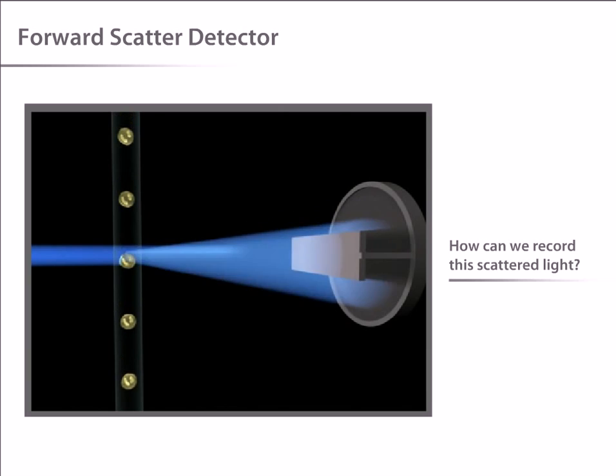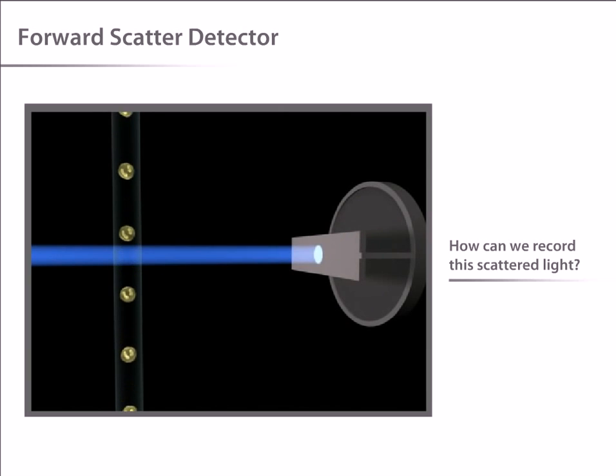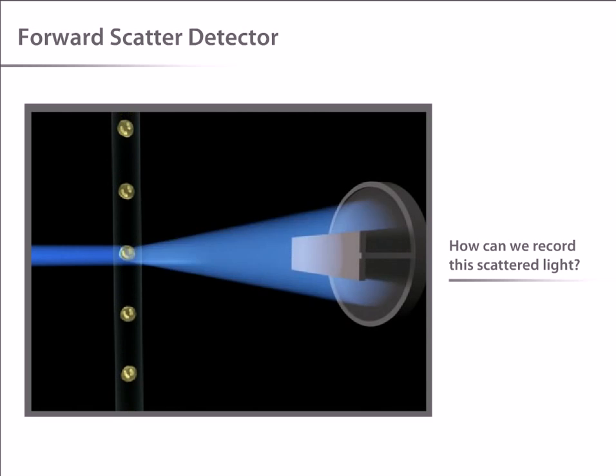The obscuration bar prevents any of the intense laser light from reaching the detector. As a cell crosses the laser, light is scattered around the obscuration bar and is collected by the detector.